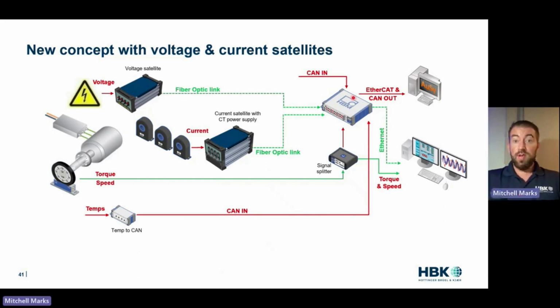And from the electrical safety standpoint, we don't have a copper cable coming back to a control room, or across the lab. That 2,000 volts is now confined to 10 centimeters, and then it's fiber optic - there's no copper connection. It's safe for people, and it's safe for the equipment.